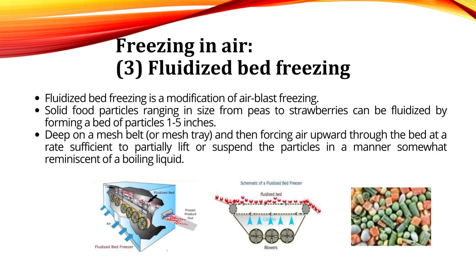Fluidized bed freezers are used to freeze particulate foods such as peas, cut corn, diced carrots, and strawberries. The foods are placed on a mesh conveyor belt and moved through a freezing zone in which cold air is directed upward through the mesh belt, partially lifting the particles so they appear to move like boiling liquid. This results in excellent heat transfer between the air and the product.